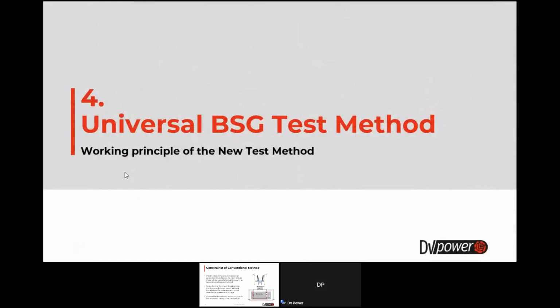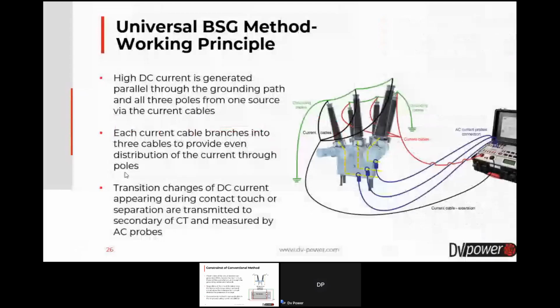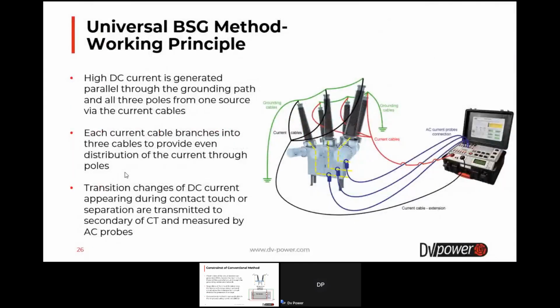So DV Power has developed a universal BSG test method that is applicable for all types of grounding which are used for dead tank circuit breakers. It is based on the generation of high DC current through the main contacts and grounding path, and the measurement of the response signal at the secondary of the current transformer. As you can see, high DC current is generated parallel to the grounding path, and all three poles from one current source, through these two cables, which further branch into three equal cables to provide even distribution of the current through each pole.